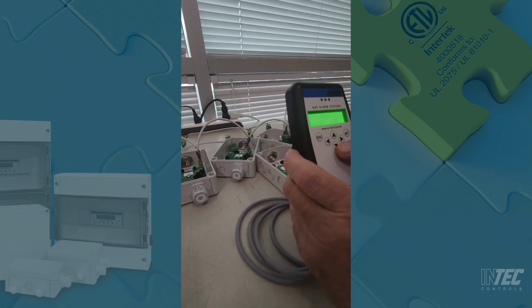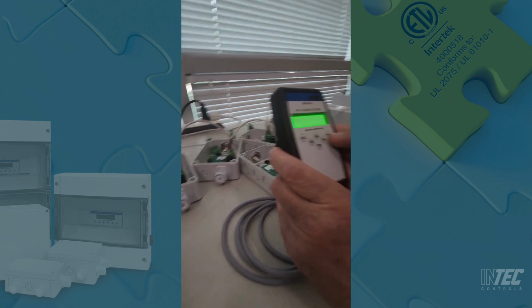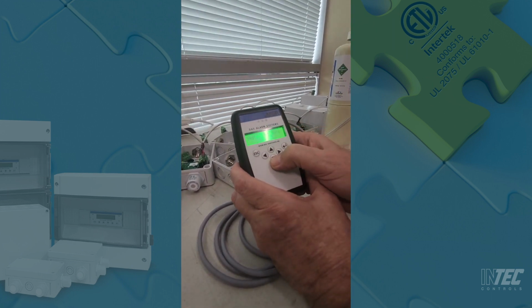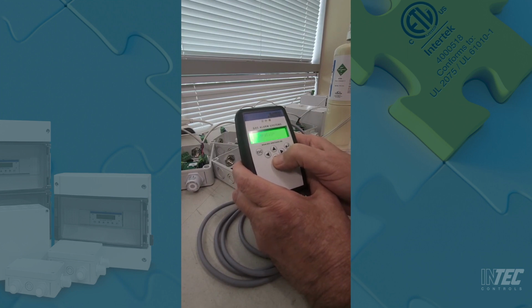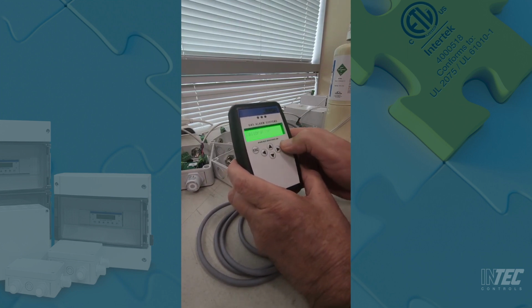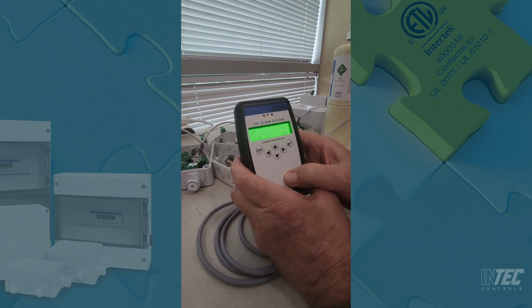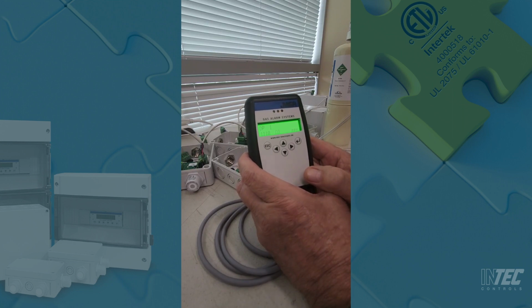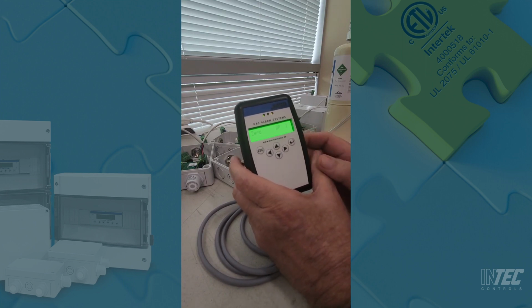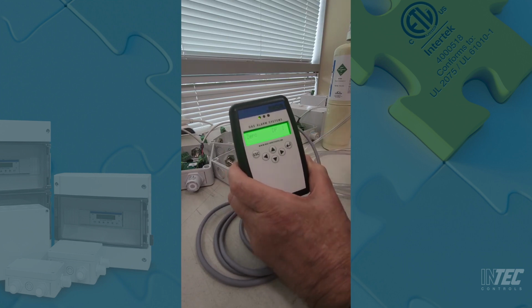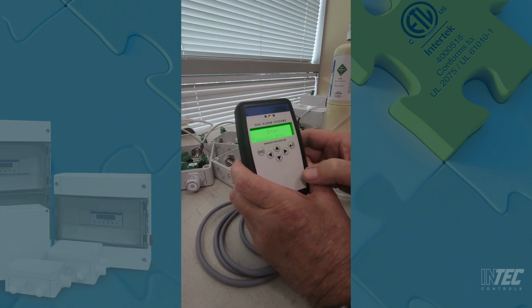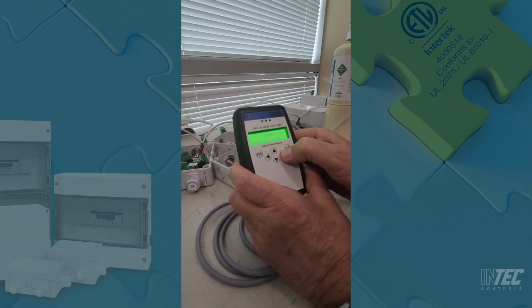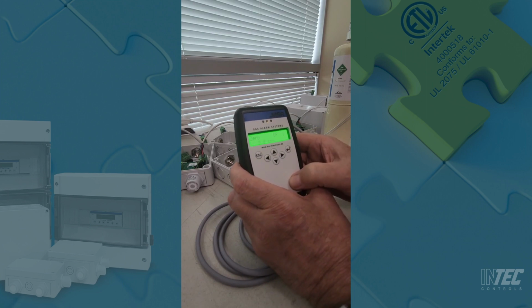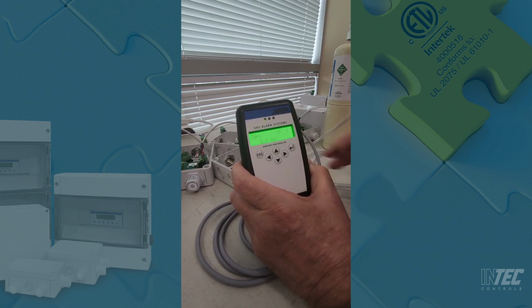So now we're going to scroll down until we see calibration. Once we're at calibration, we're going to hit the enter button. It shows DP1 1110, it's a seal sensor. It already knows it on there. What we're going to do now is hit the enter button to go into DP1, digital point number 1, to zero it out. At this time, I'm going to go ahead and hit the enter button. It's going to ask for the password, and it shows the current value of the sensor.